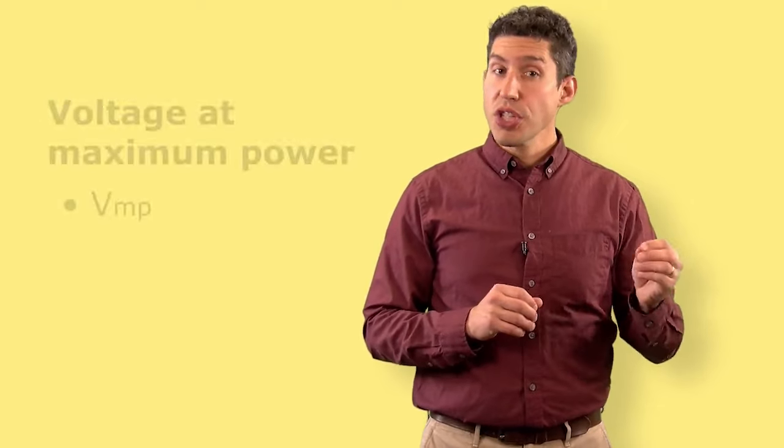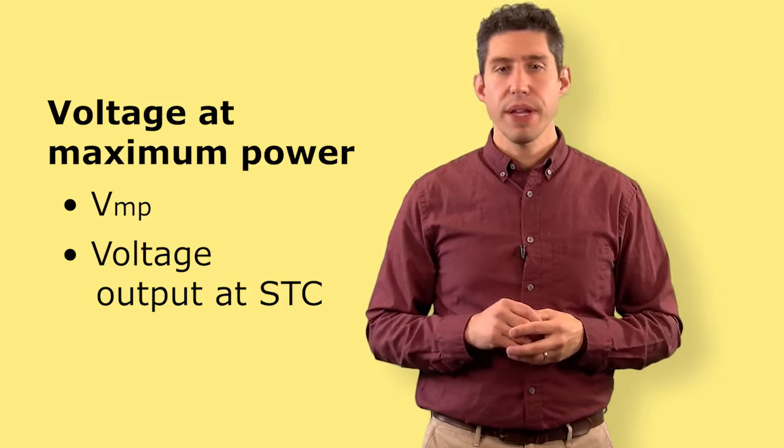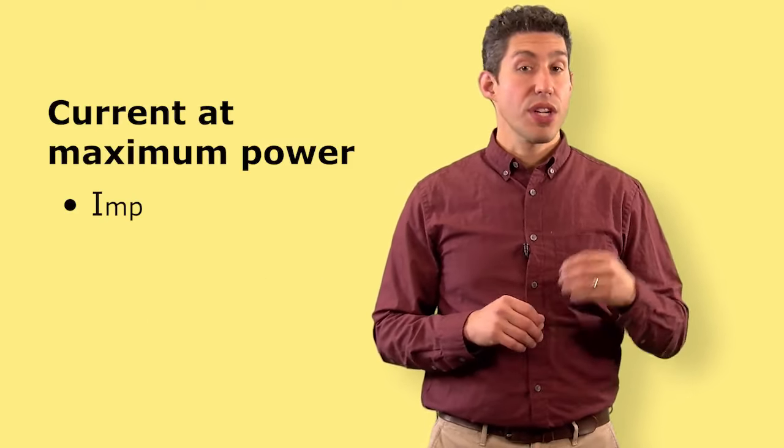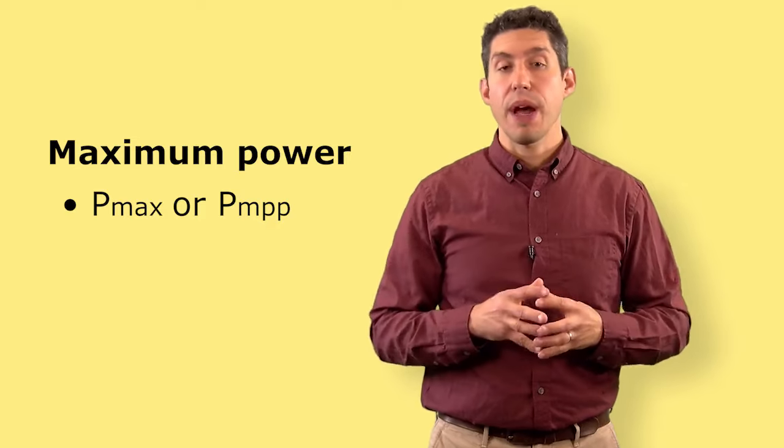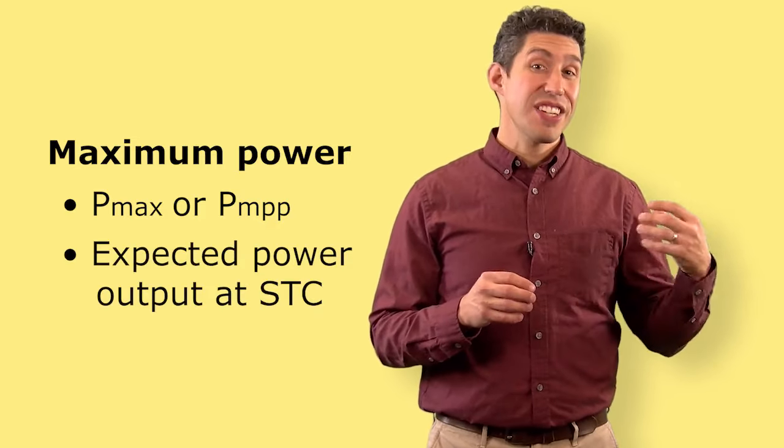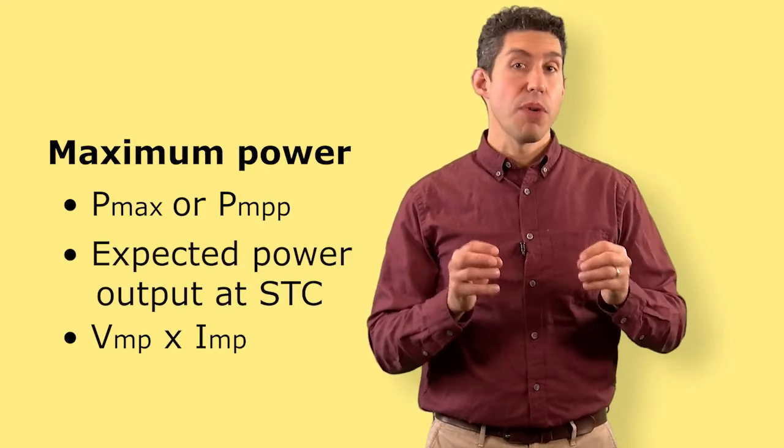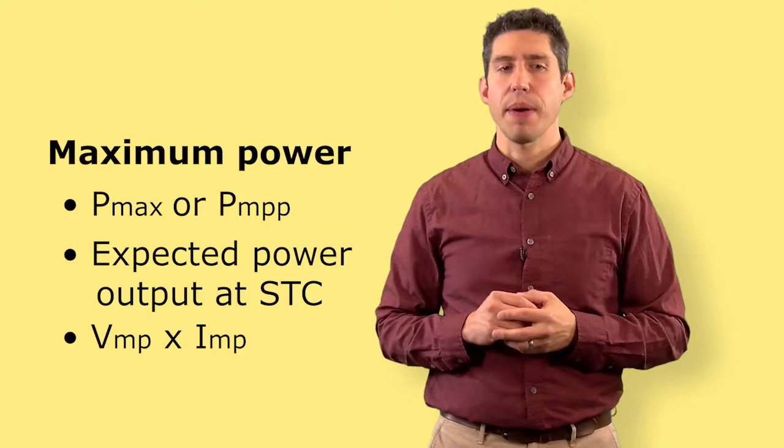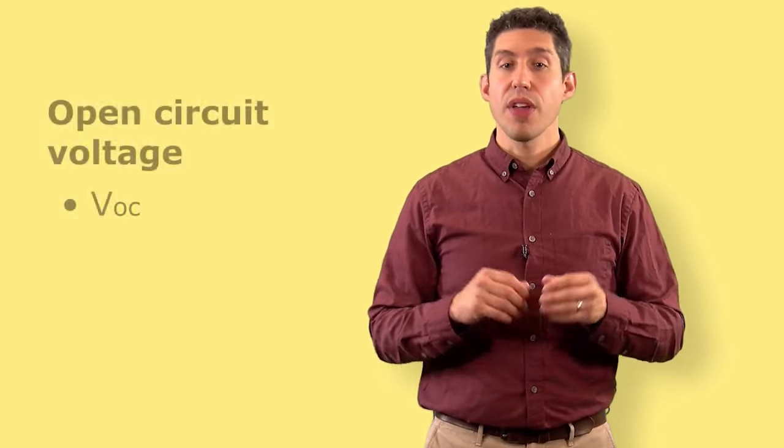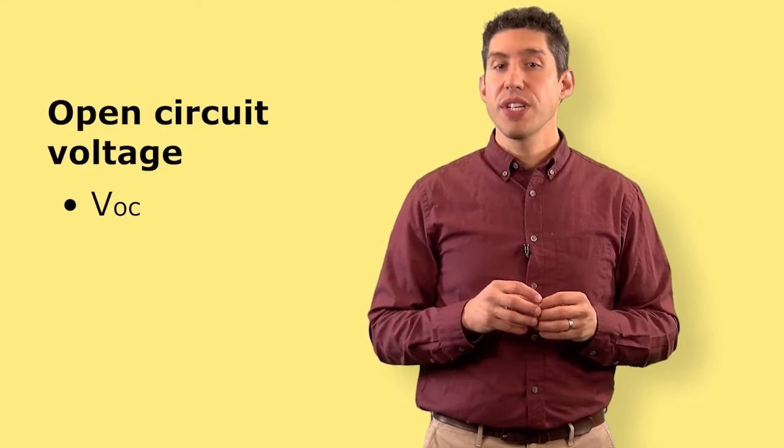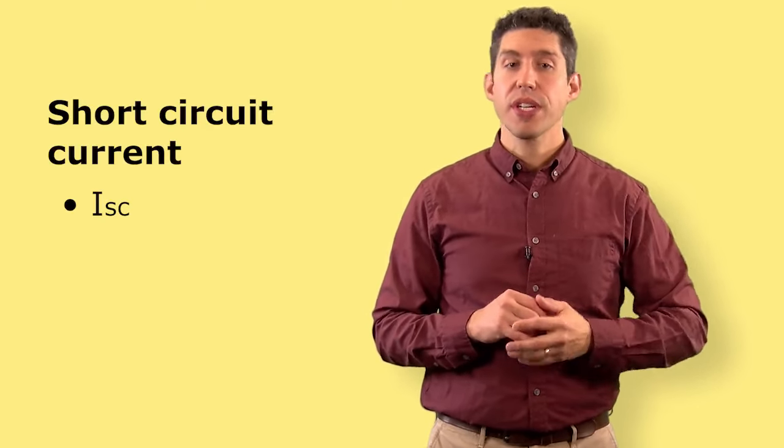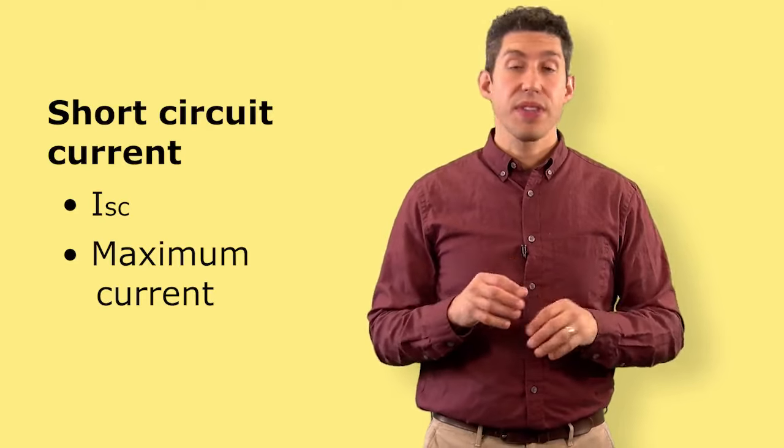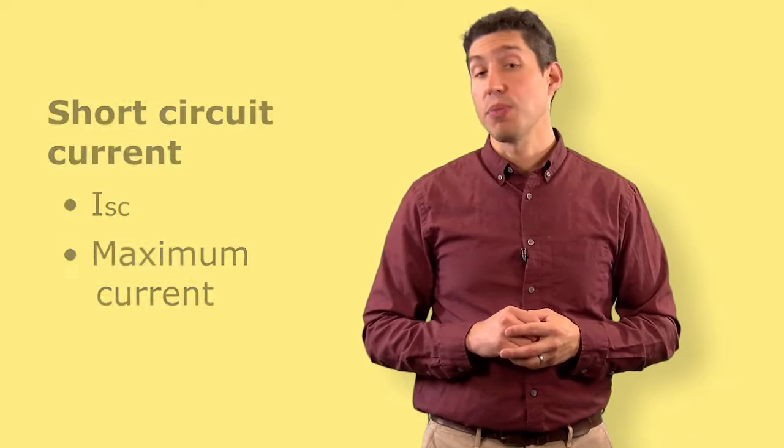The five terms are the voltage at maximum power, which is the voltage being put out by the solar panel, the current at maximum power, which is the current that's being put out under maximum power, and the power, or maximum power, which is the power of the solar panel, which is actually a calculation of the voltage at maximum power multiplied by the current at maximum power. The other two key terms are the VOC, or open circuit voltage, which is the maximum voltage that the cell will ever put out, and the ISC, or short circuit current, which is the maximum current the cell will ever put out, or the module will ever put out. We'll look at these two terms more in another segment.